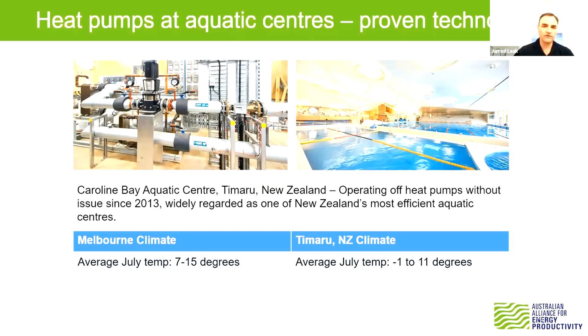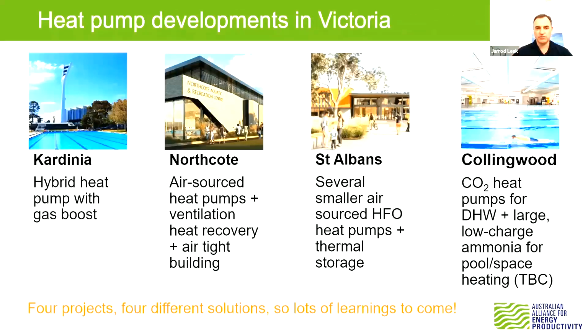And so they are one of 4 major aquatic centre upgrades going on right now, and each of them is doing it slightly differently. So there'll be a lot of lessons learned coming from this. We have Cardinia and Geelong looking at doing a hybrid heat pump combined with a bit of gas boosting. Northcote are doing an air sourced heat pump, with ventilation heat recovery and a really airtight, strong building. St Albans, I understand, are using several smaller heat pumps, this HFO type, as well as thermal storage.